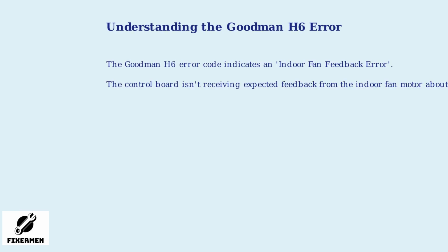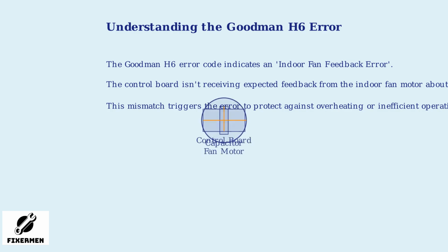The Goodman H6 error code indicates an indoor fan feedback error. This means the HVAC system's control board isn't receiving the expected feedback from the indoor fan motor about its speed. This mismatch, detected via sensors, triggers the error to protect the system from overheating or inefficient operation.